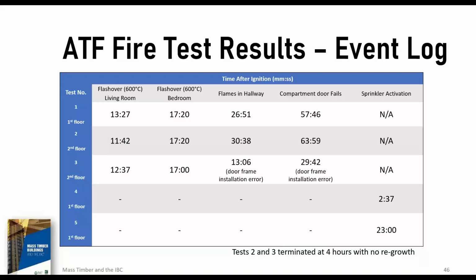Again, that open door really facilitated the heat and smoke and flame going into the other side of the unit. And flashover occurred within 20 minutes over all 3 tests. So as we showed you in the video, we had some flame front penetration of the 20-minute compartment door in the hallway. We went almost 27 minutes before we had flames in test number 1, a little bit longer at 30 minutes, give or take, in test number 2.